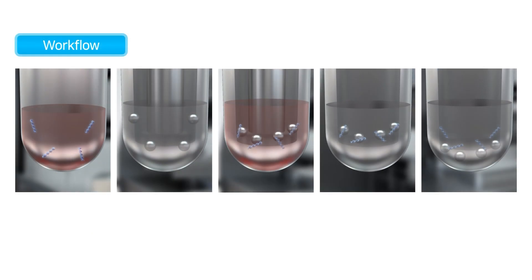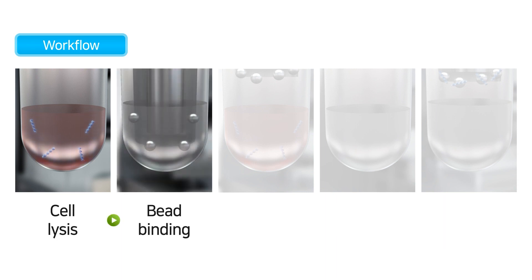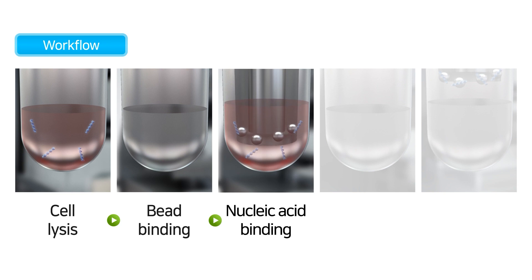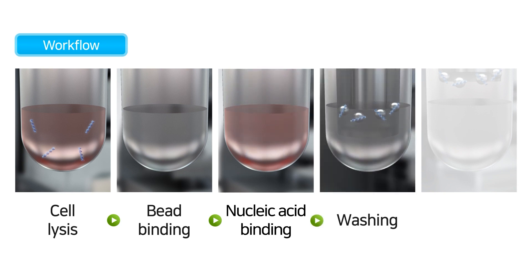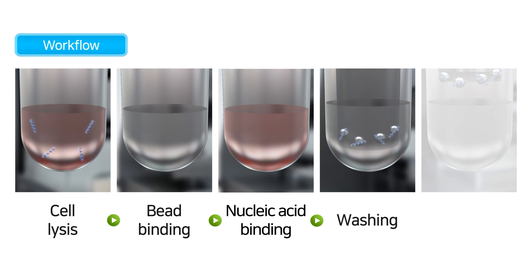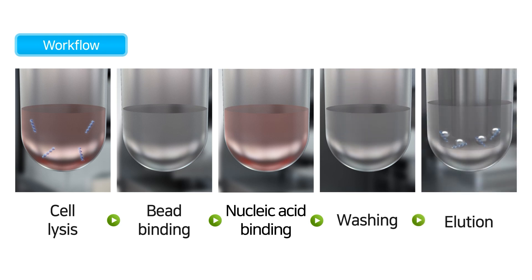The Exaprop 96 Light has five steps for nucleic acid extraction using its magnetic rods: cell lysis, bead binding, nucleic acid binding, washing, and nucleic acid elution.